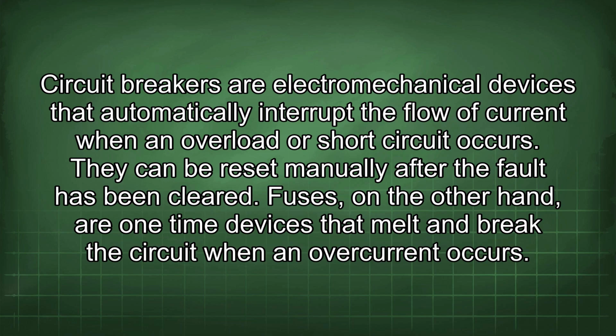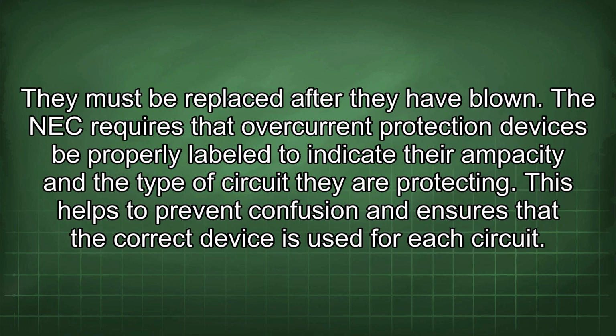Fuses, on the other hand, are one-time devices that melt and break the circuit when an overcurrent occurs. They must be replaced after they have blown. The NEC requires that overcurrent protection devices be properly labeled to indicate their ampacity and the type of circuit they are protecting. This helps to prevent confusion and ensures that the correct device is used for each circuit.